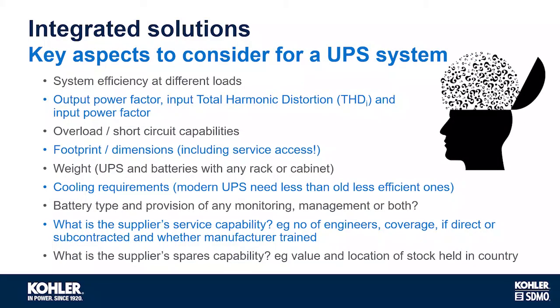So some of the things we need to consider with the UPS and the whole system is, how efficient is that UPS? And it's not just about the efficiency at 100%. Most UPSs, due to the redundancy, don't run at 100%. So it's very important that we understand the efficiency at the load we're planning to run at. We need to understand that the power we gain is what we expect. So understanding the output power factor of that system to make sure we're running the kilowatts we need.